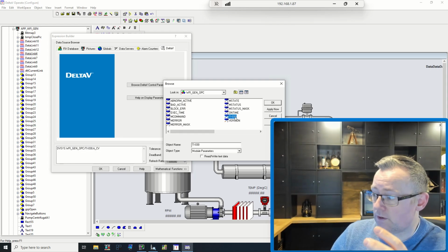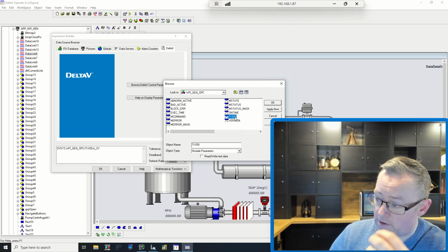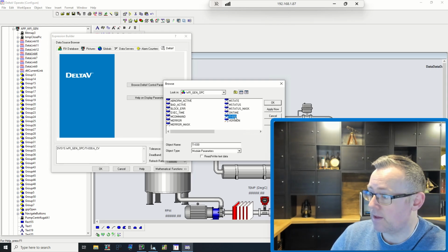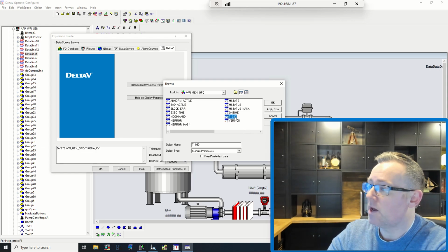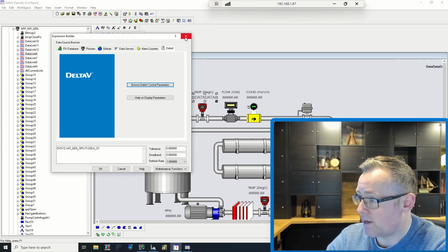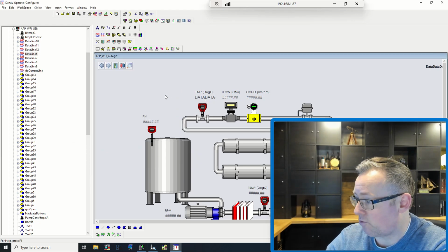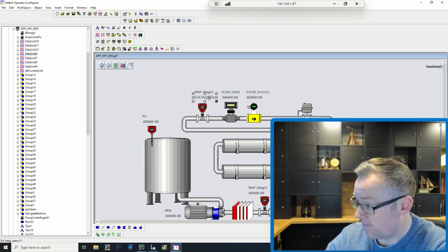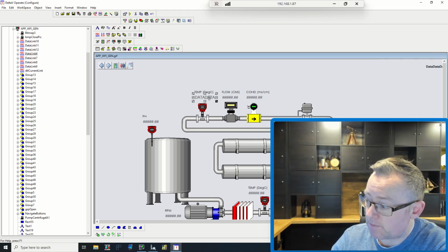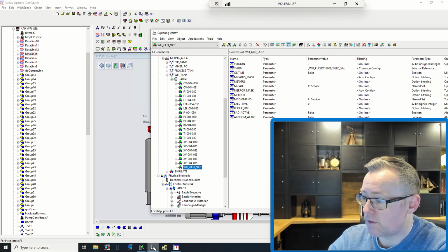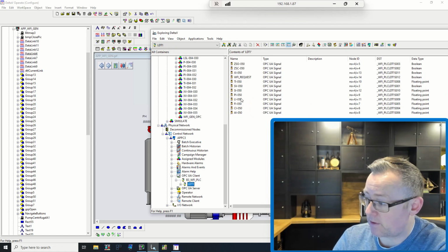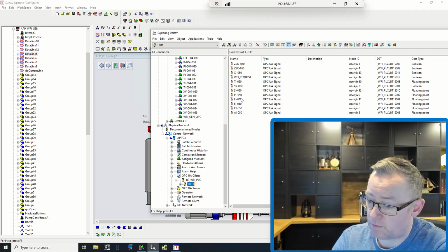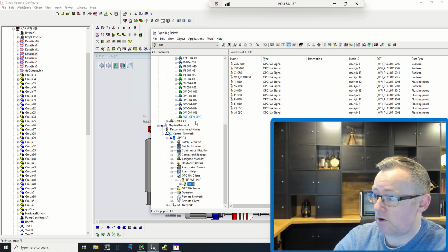So the core thing was, in order to get it working, I created a control module purely for holding variables, which pointed out to the OPC variables themselves. I don't understand exactly the reason 100%, but if you try to display the direct OPC UA variables here, they won't display properly. So that's effectively where people were going wrong. Hopefully this clears up any confusion. Thank you very much.